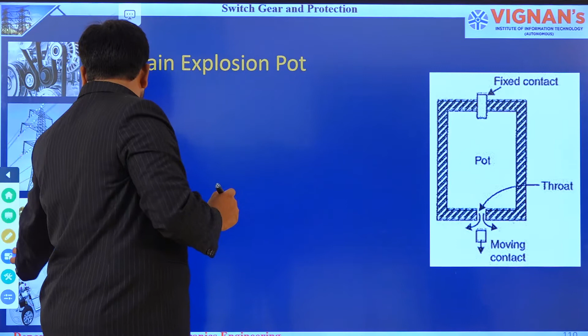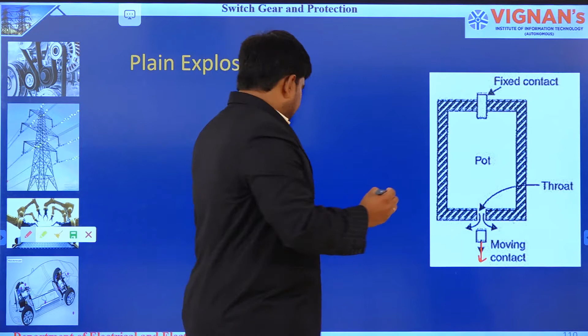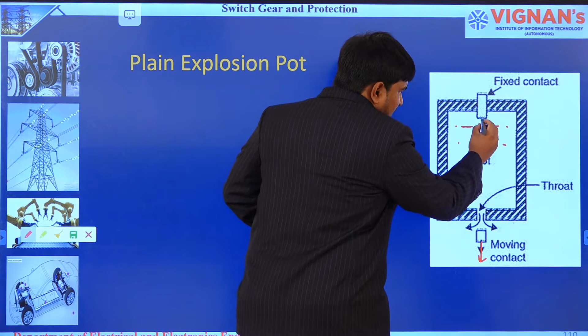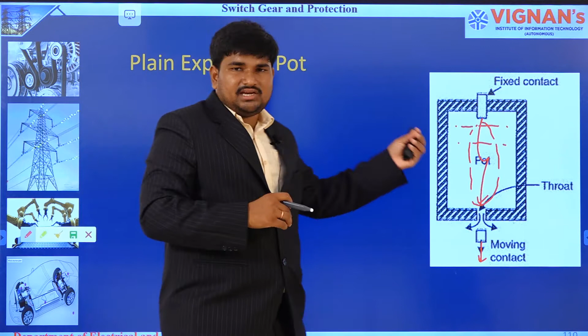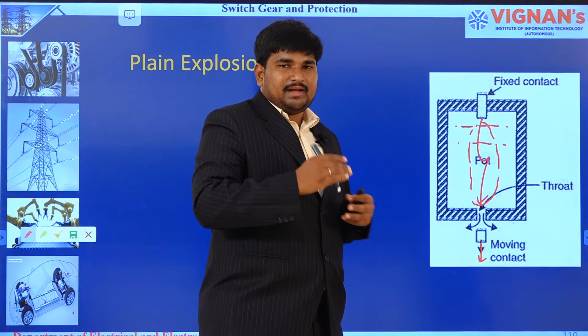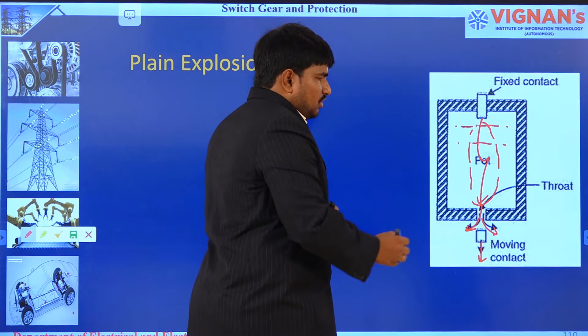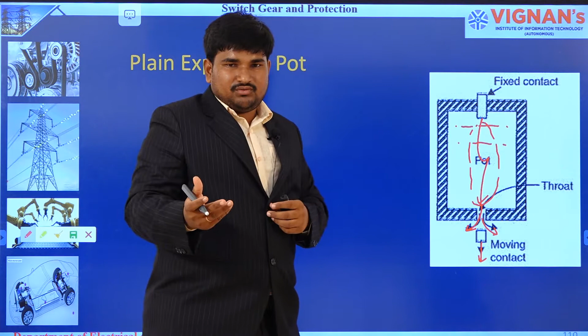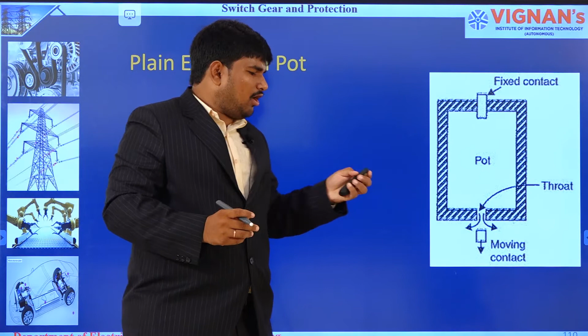For example, an abnormality occurs. The moving contact needs to move away from the fixed contact, and the oil will be there. In between these contacts there is an arc. Because of that arc, the total area around it will be heated up. The heating of oil causes production of gases, as we have discussed earlier. So hydrogen and methane gases become pressurized and come out, and in this process the arc becomes extinguished. That is the concept of the plain explosion pot.